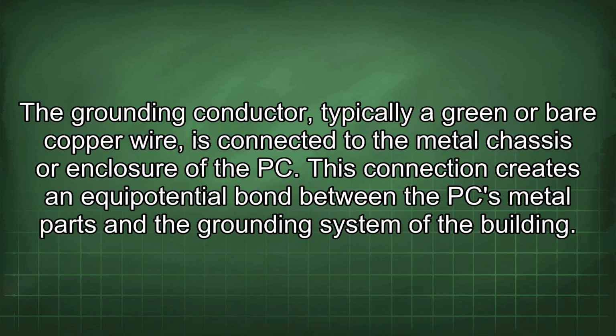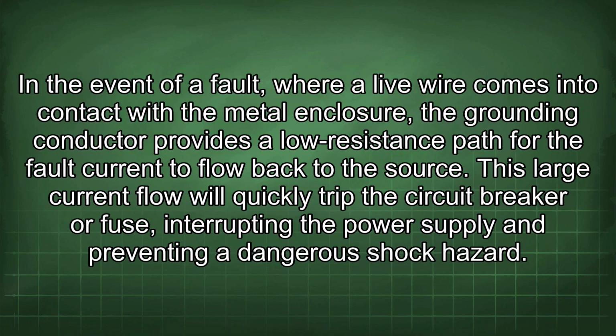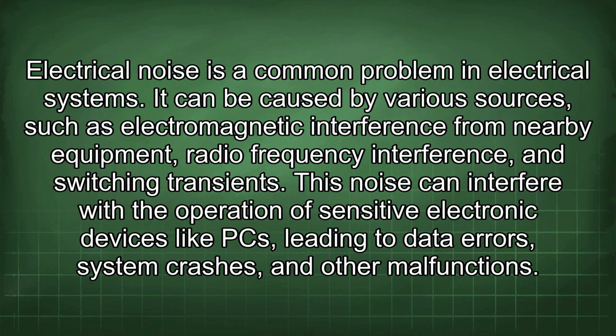The grounding conductor, typically a green or bare copper wire, is connected to the metal chassis or enclosure of the PC. This connection creates an equipotential bond between the PC metal parts and the grounding system of the building. In the event of a fault, where a live wire comes into contact with the metal enclosure, the grounding conductor provides a low resistance path for the fault current to flow back to the source. This large current flow will quickly trip the circuit breaker or fuse, interrupting the power supply and preventing a dangerous shock hazard.